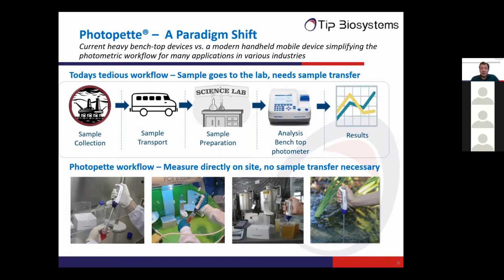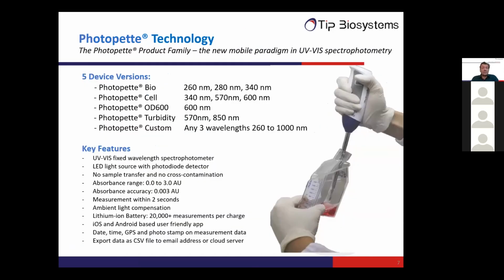They might aggregate and change their turbidity, or the turbidity caused by algae and things like this, and they still grow. So by not measuring at the site, your sample will actually change. You have a very accurate measurement in the lab, but unfortunately, your sample is no longer your original sample. So those are the advantages that you can capture with a Photopette device to measure directly on site.